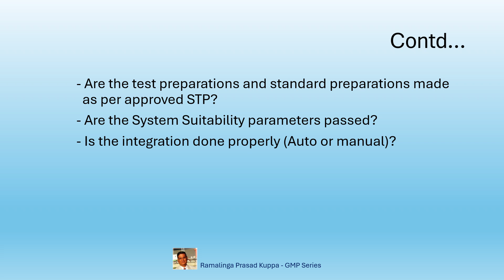Is the integration done properly, auto or manual? Most of the integration is done automatically, but it is important to check whether the integration of tailing peaks or fronting peaks are not shaved or extended to get a different value. There should be a procedure for manual integration also in case necessary. All auto integrated peaks are not always correctly integrated.